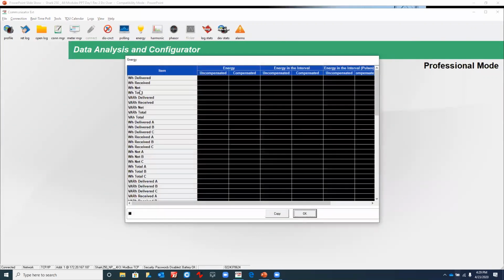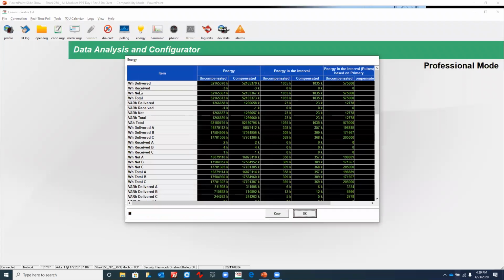Then you will find the energy grid. So here you find, as we saw previously, energy readings on the display. If the meter was programmed for compensation, where we were compensating for line losses or transmission line losses or things like that, you will see the uncompensated value here, and then the compensated. In this particular case, they're pretty much identical, so it tells me that meter was not adjusted for compensation.